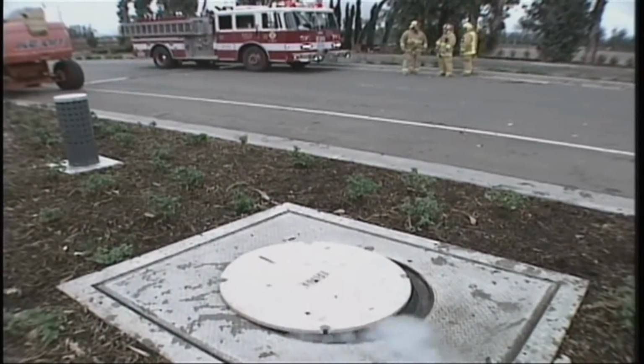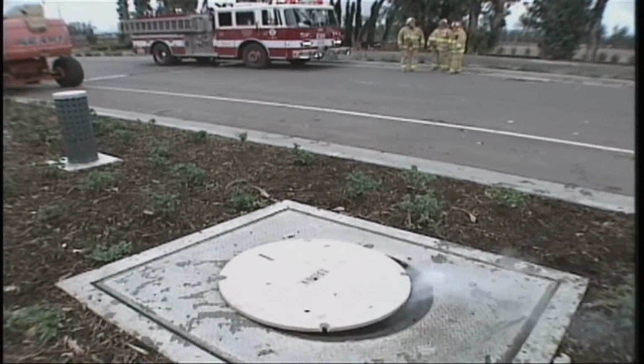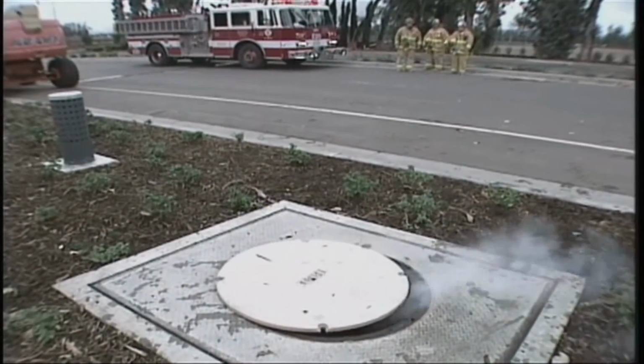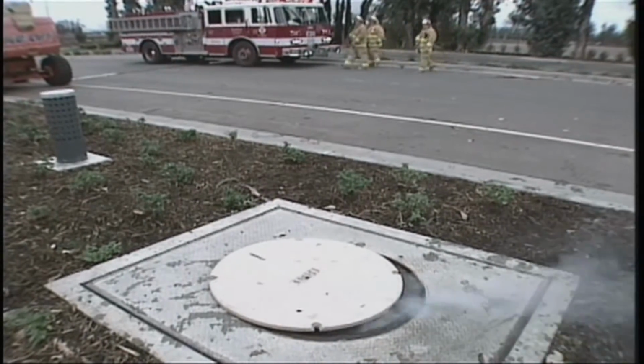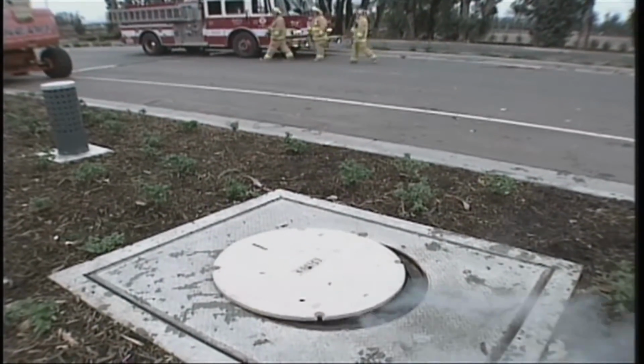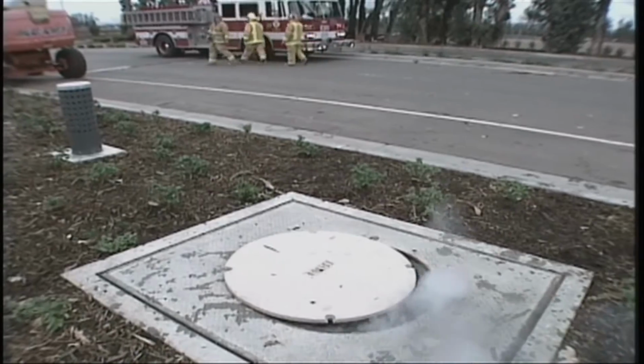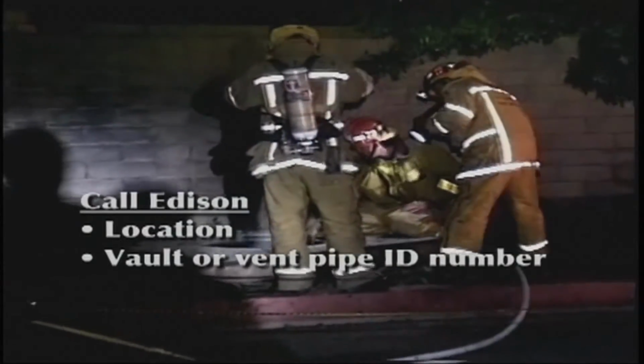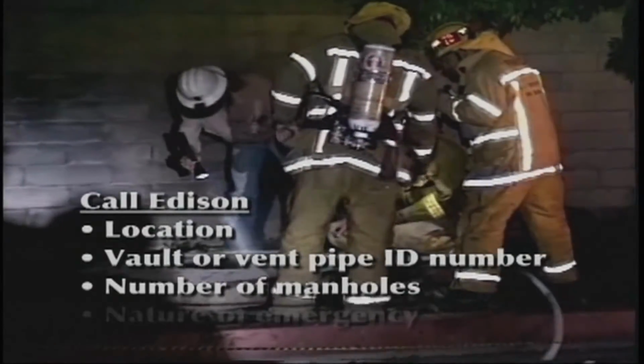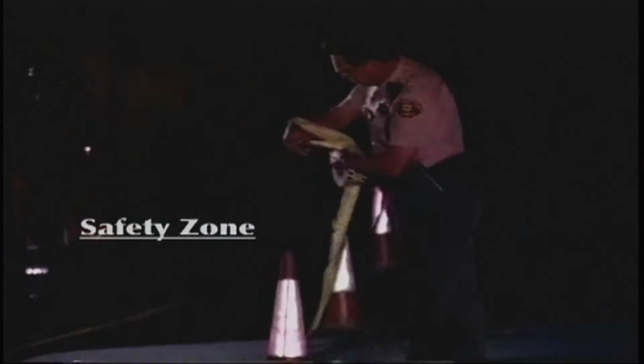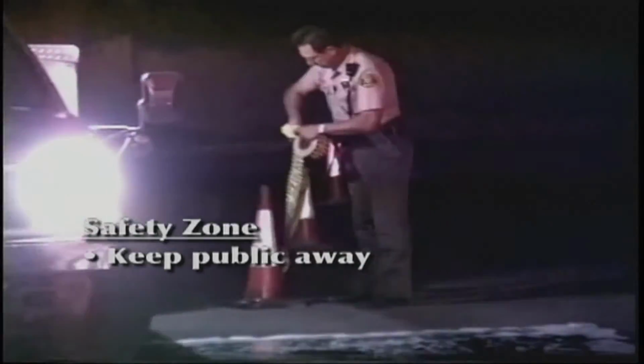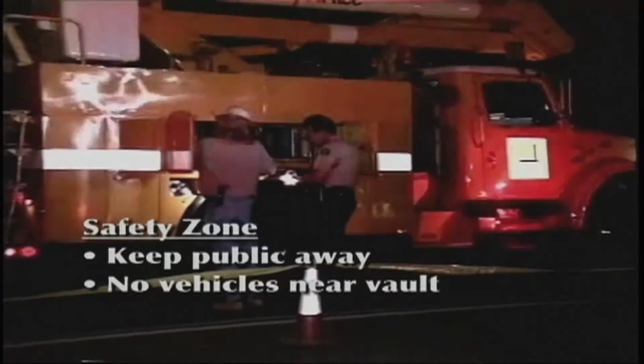In the underground environment, one failure in the system has the capacity to cause additional equipment or cable failures. The resulting explosions could seriously harm you and others nearby. Here's what to do. Call Edison. Give the location, the vault or vent pipe identification number, number of manholes involved, and the nature of the emergency. Establish a safety zone. Keep the public away and route traffic around the area. Don't park vehicles near vault or manhole covers or vents.